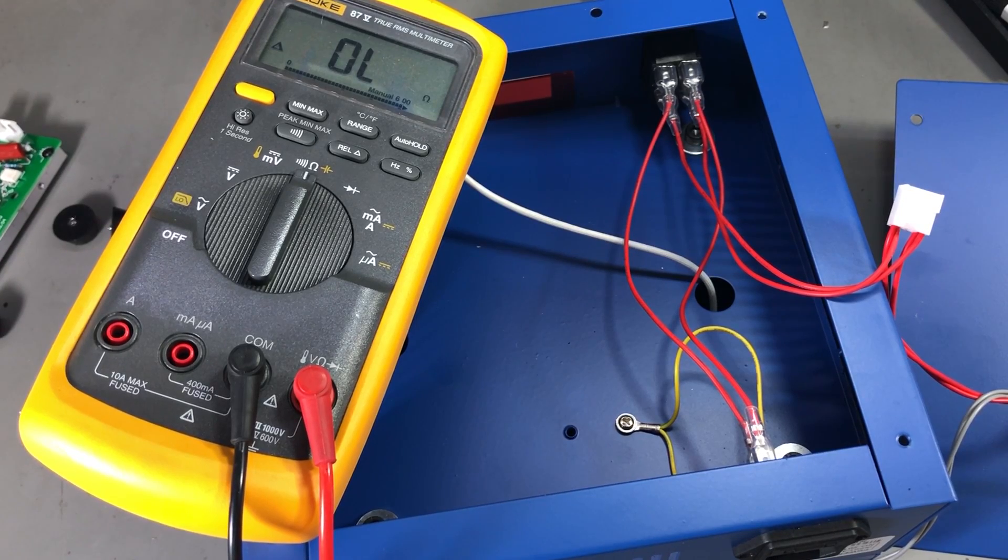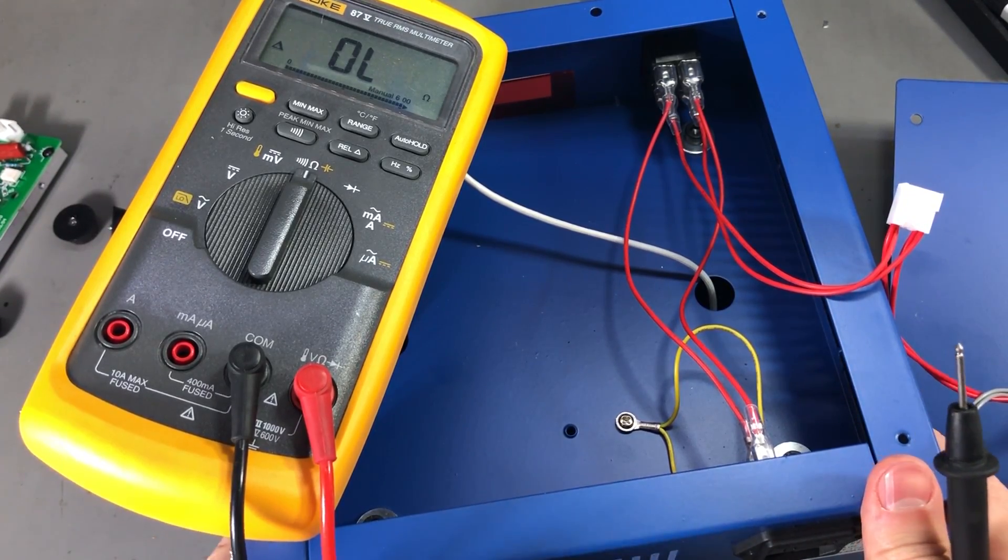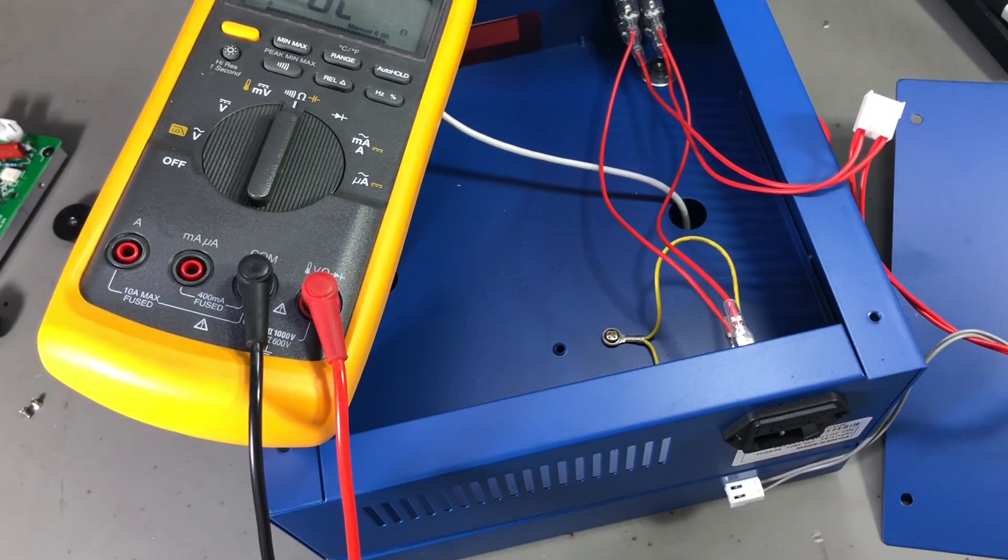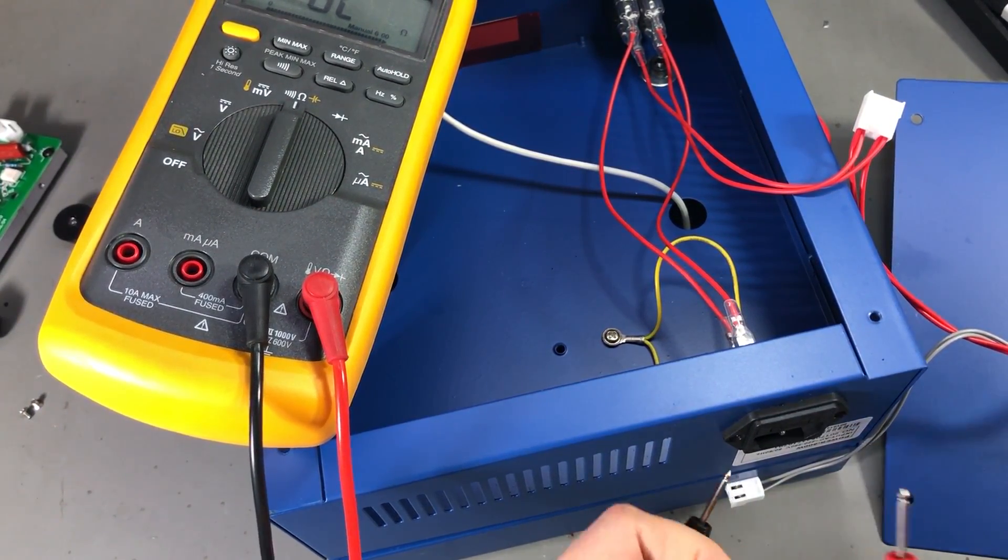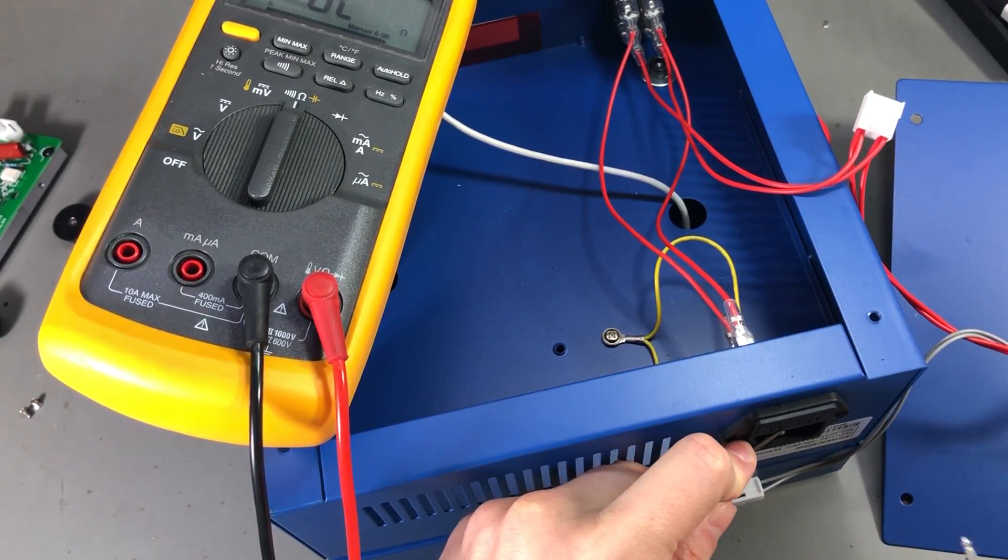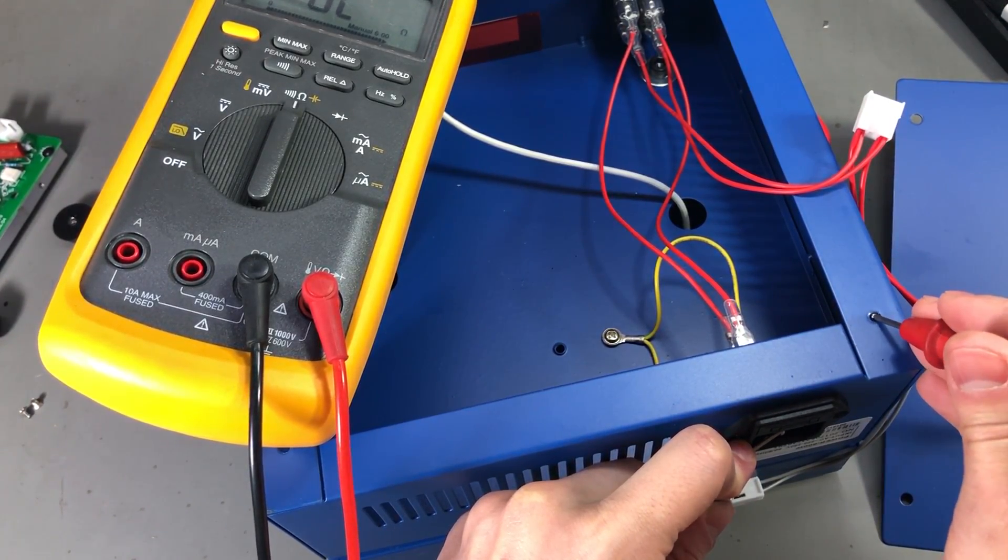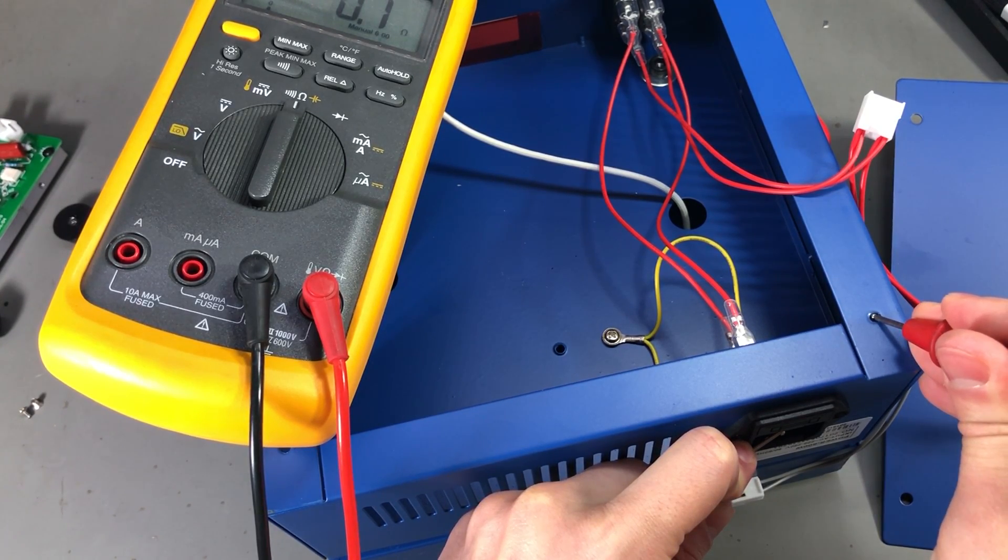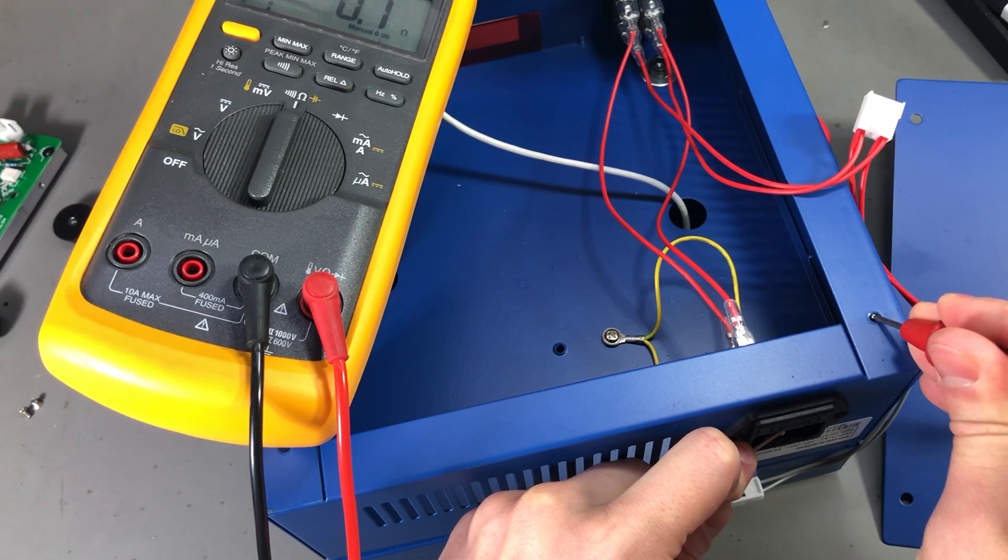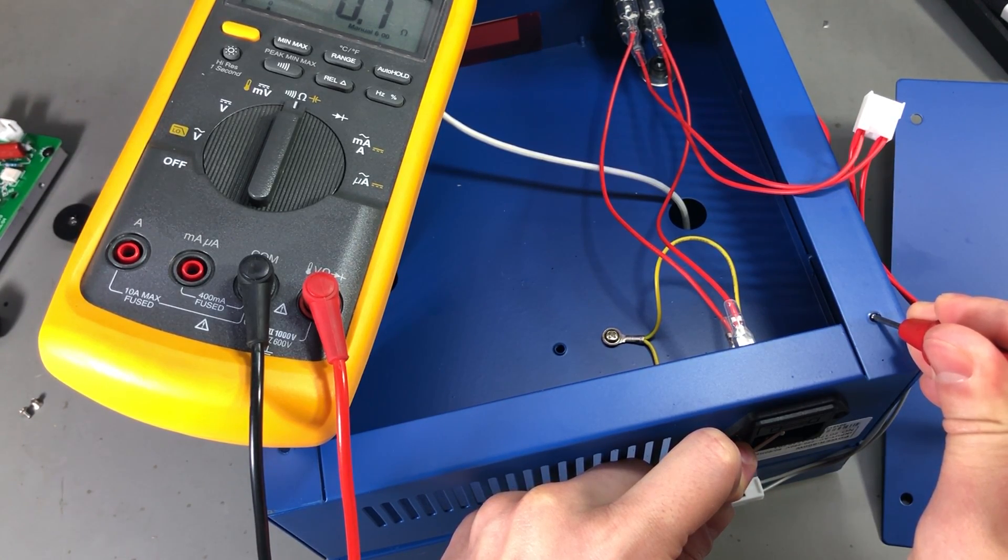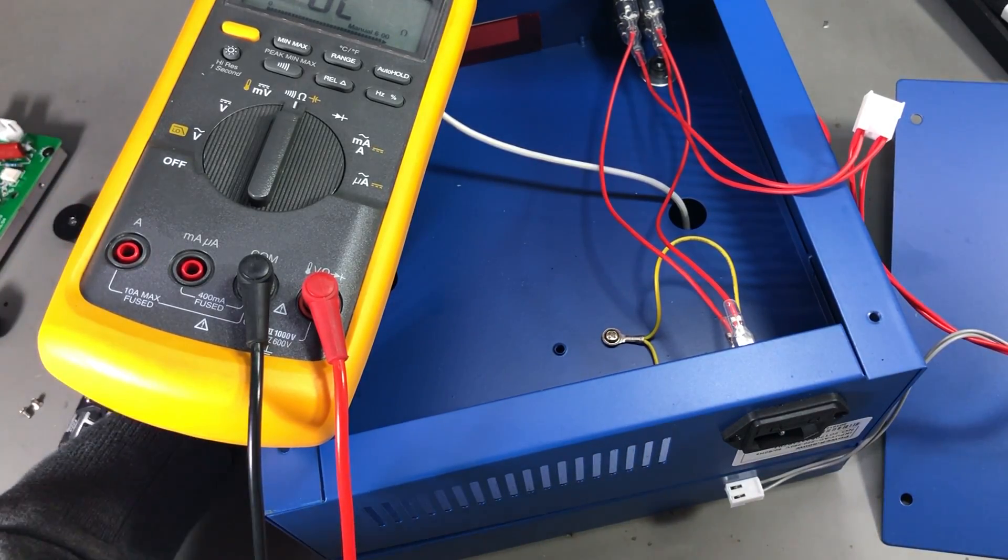Before scraping away the paint on that ground point let's try to measure from the IEC main socket up to a point on the metal chassis and see what kind of resistance we're getting. So let's try to measure to this screw hole and we're getting 0.1 ohms. So even though it has paint on that surface it's not really a bad grounding on this product because it's just 0.1 ohms.